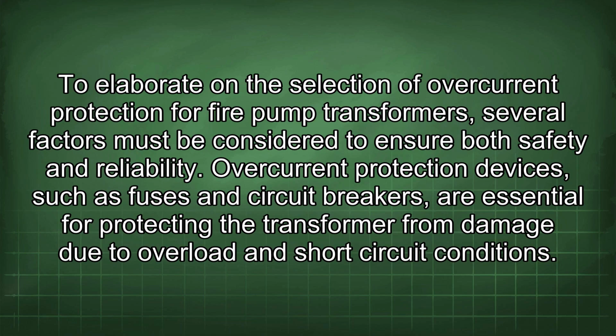To elaborate on the selection of overcurrent protection for fire pump transformers, several factors must be considered to ensure both safety and reliability. Overcurrent protection devices, such as fuses and circuit breakers, are essential for protecting the transformer from damage due to overload and short-circuit conditions.